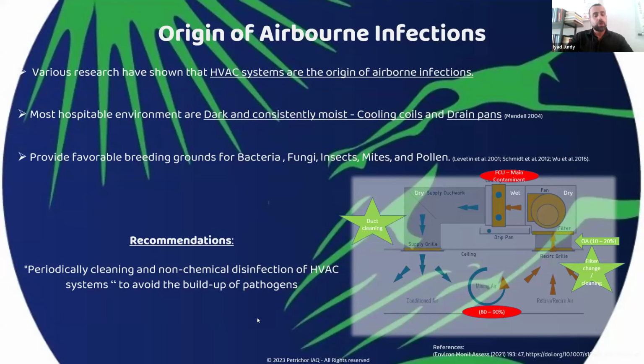So long story short, the recommendation is periodic cleaning, non-chemical disinfection of the HVAC systems. And here I always stress non-chemical, not only because of the business we're in, but mainly because if you put chemicals on the coil, you're going to get all the TVOCs going all over the place. Then you evacuate and you're pretty much shooting yourself in the foot, because you're putting chemicals or acid, damaging the coil just to kill a few bacteria, which doesn't always work.